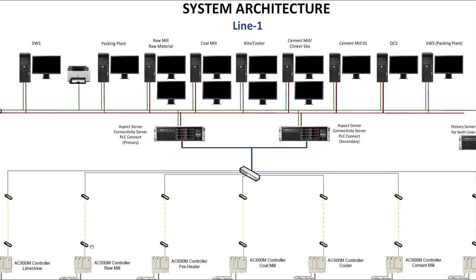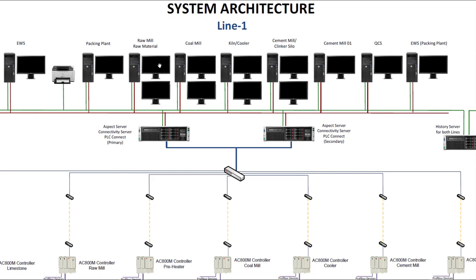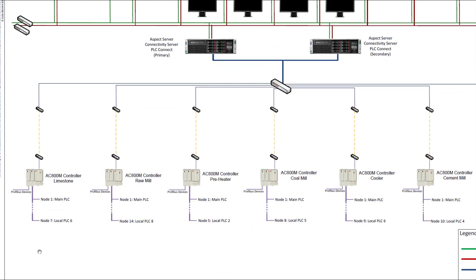The servers also write data into the PLCs through the graphical interfaces. An operator monitors the process values through the graphical interface and issues commands to the motors, valves, and actuators to control the process according to requirements. The graphical user interface is displayed to the operators through their operator station monitors. Every area has its specific operator — for example, packing plant, raw material, coal mill, kiln, and so forth — and these monitors display the graphical interfaces served by the servers, showing all the process parameters coming from the field sensors.